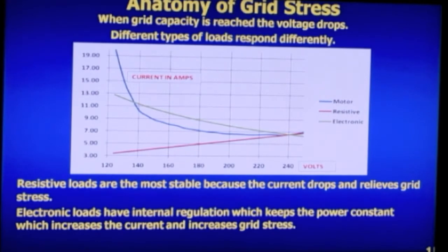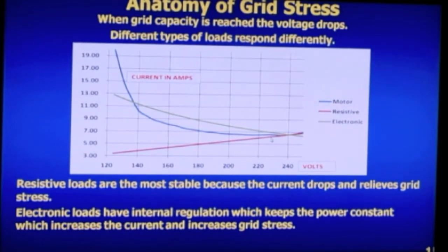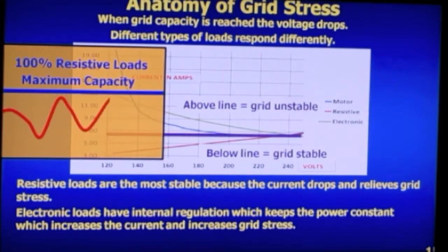What's the difference? A resistive load, like this red line, if you lower the voltage, it lowers the current. But an electronic load is smart, if you lower the voltage, it automatically increases the current. The voltage drops because the grid or generator has reached capacity, and increasing the current just makes it worse. In the old world, if loads exceeded the grid, the voltage would just dip a little and light bulbs would dim, then get bright again, you've probably seen that when a big motor starts.